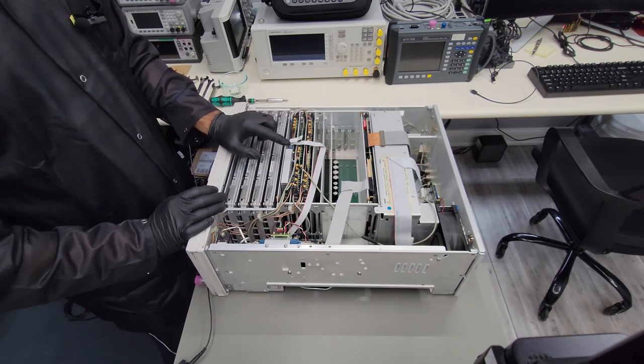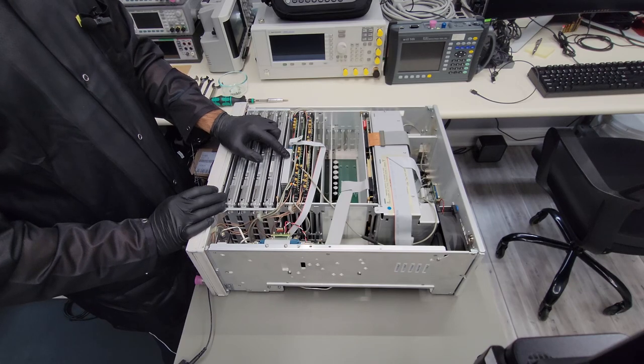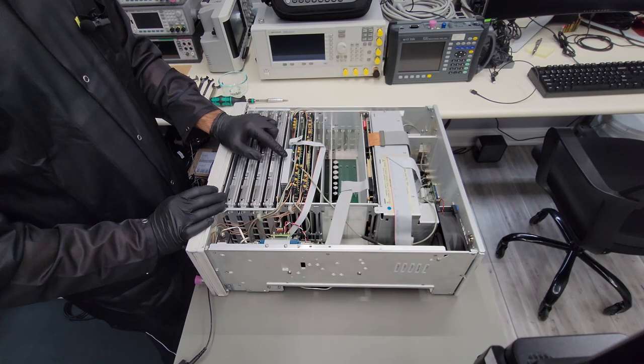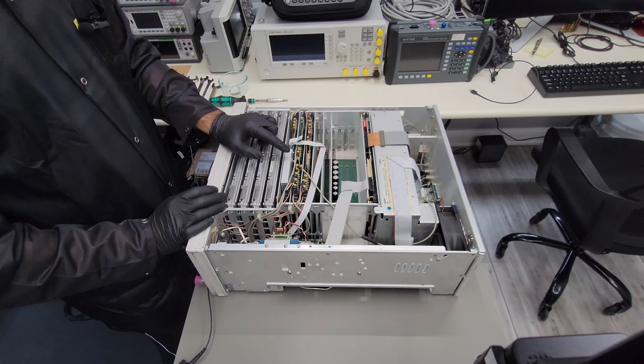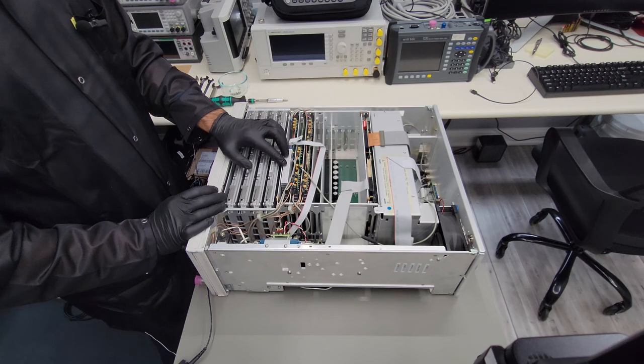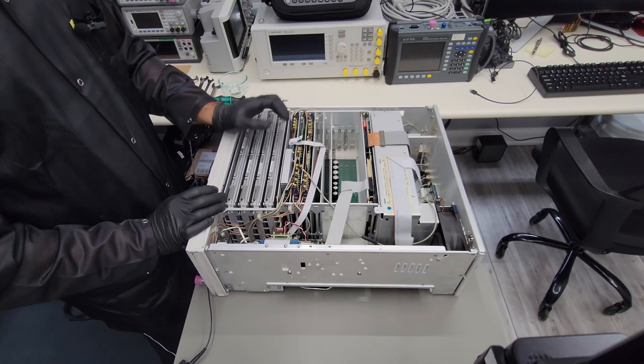So we have the YIG driver here. This is responsible for controlling the fundamental signal source in this instrument, which is a 3.2 to 10 gigahertz YIG tuned oscillator. So this is the board that provides the current and the control for the YIG.